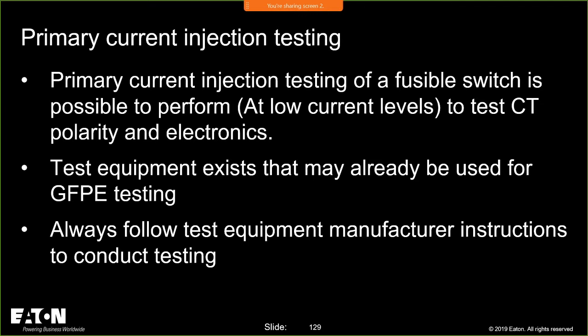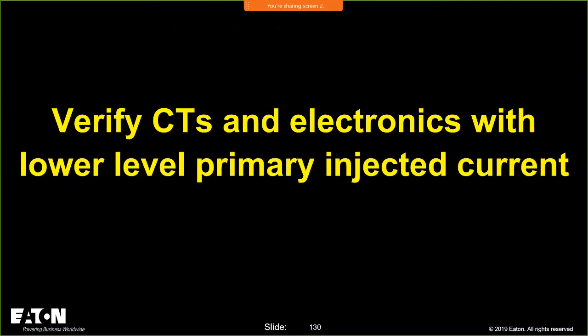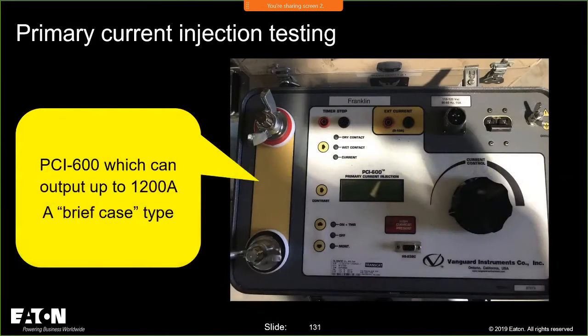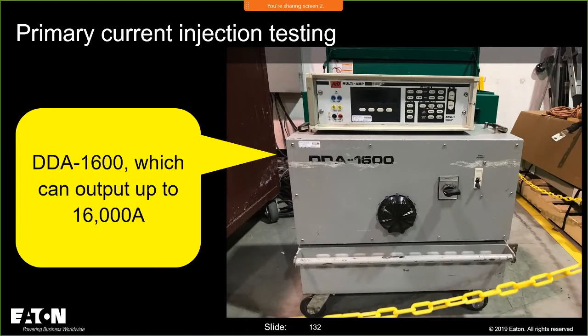Primary current injection testing, you're going to verify the CTs. Here is some of the equipment that we use. This is a PCI 600, outputs of 1200 amps. It's briefcase size, easy to carry around, but the output's only up to 1200 amps. This is the DDA 1600, 16,000 amps of pure fun in the field.